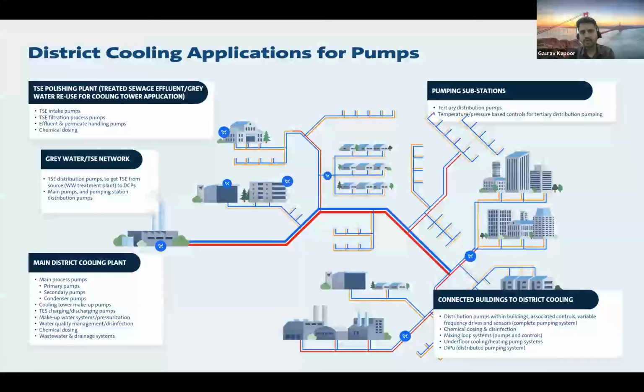Now, if we look at district cooling application from a pumps perspective, where the pumps are being used in a district cooling network: obviously in the main district cooling plant, you have process pumps, meaning primary, secondary and condenser, large size process pumps, which we will discuss in further slides. Then cooling tower makeup pumps, then thermal energy storage charging and discharging pumps, makeup water pumps, chemical dosage pumps. Then besides the main district cooling plant, there are TSE polishing plants also. TSE, as sir talked about, is treated sewage effluent or grey water reuse for cooling tower application. There also a lot of pumps are required, and in a few countries in the world TSE is mandatory to be used in a district cooling plant to save on the water requirement in the cooling towers, because a lot of water gets evaporated during the operation of the plant. Then the grey water TSE network, meaning the grey water which needs to reach the TSE plant, also requires pumps.